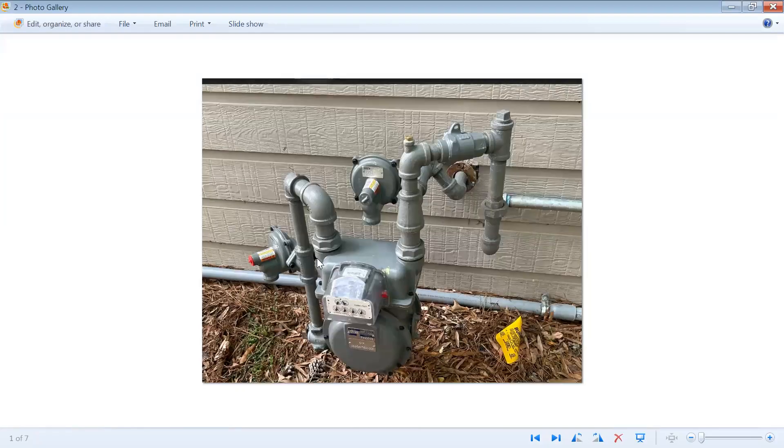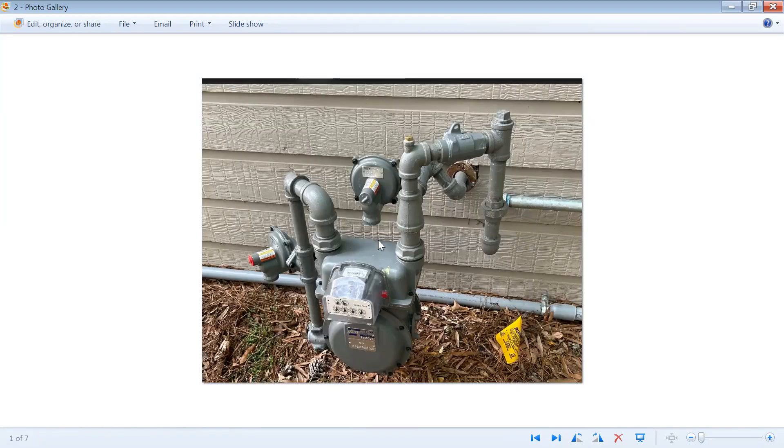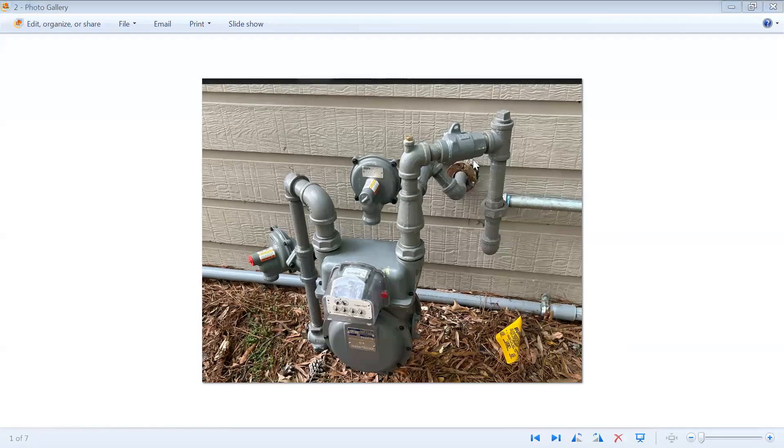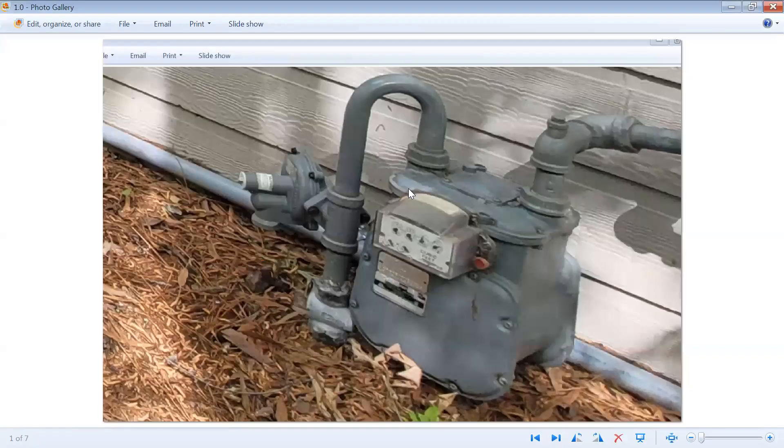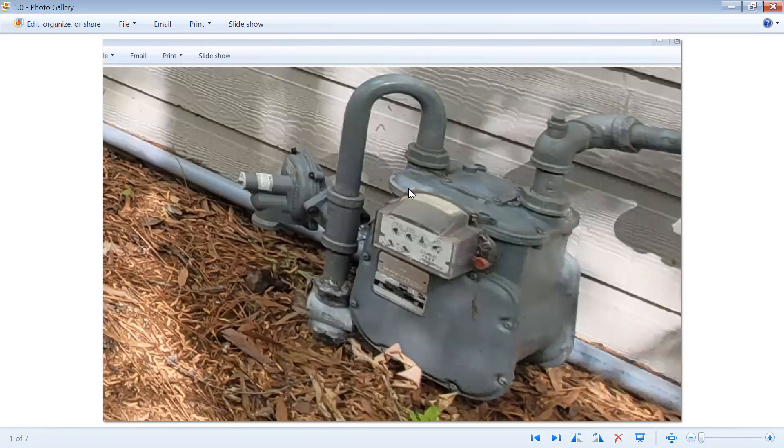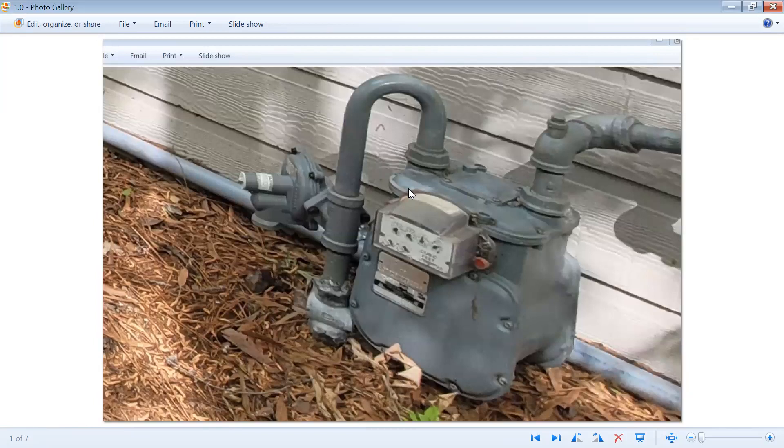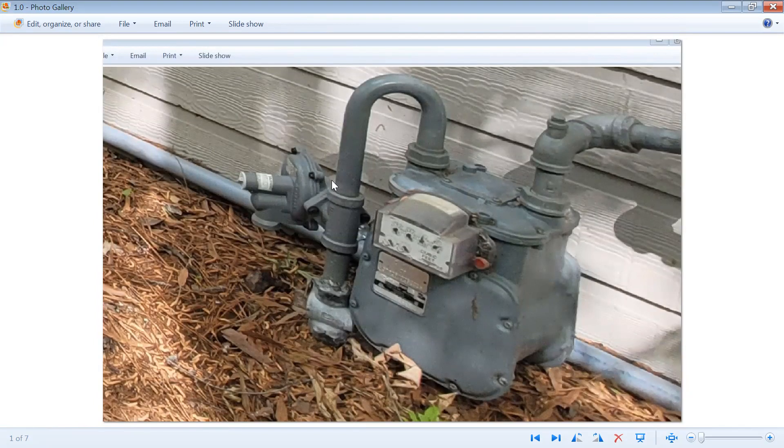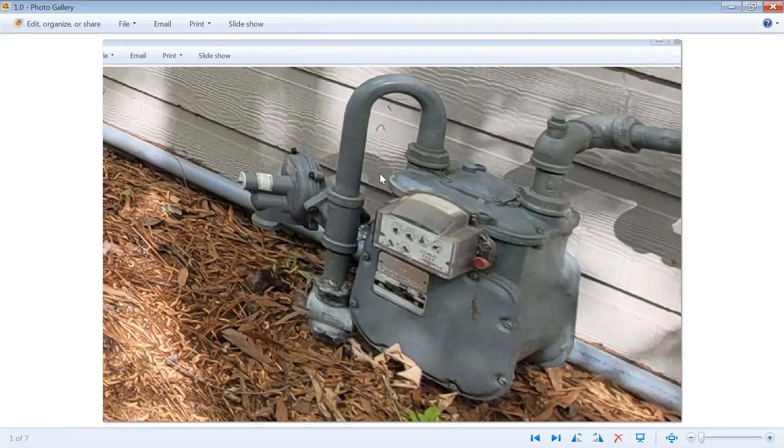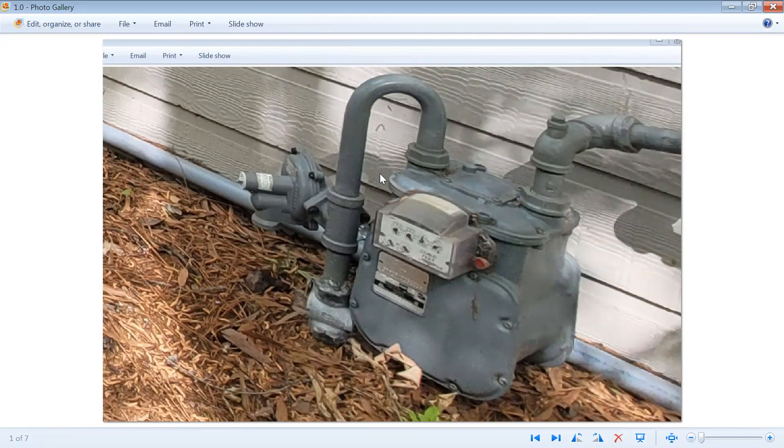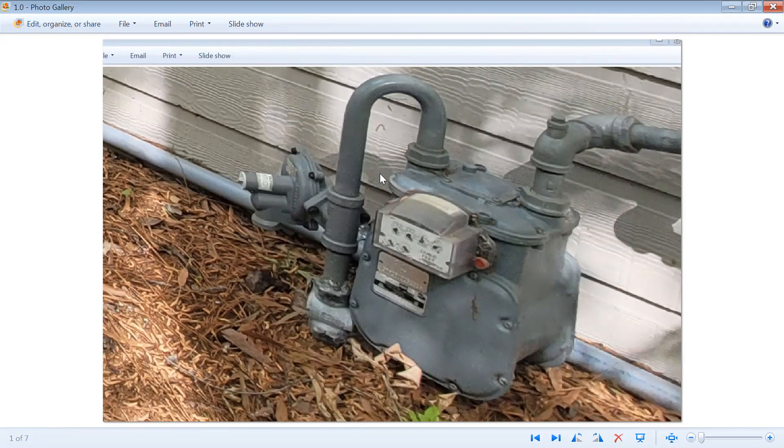Another common error is custom builders will run a single line through the house and then off that single line they will branch it off, tee it, and do a drop on the other side of the house where the pool heater and generator will be. But the problem with that is that Center Point will only install a half-pound regulator onto that meter. They will not put a high pressure regulator on the meter, and so what happens is the generator and the pool heater cannot run because they will be starved of gas.